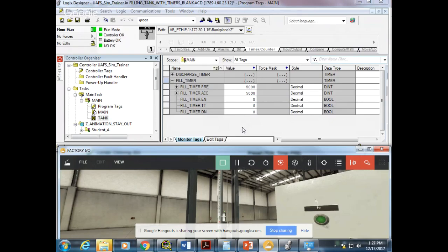So what could I use that for? Let's say I have some kind of mill or machine with a heavy torque load, like a 50 horsepower motor. Okay. And so when I hit the off button, I really don't want to just turn it off. I want to turn it off, but I want to apply the brakes for 20 seconds. And I could use that TT bit to apply the mechanical braking system for 20 seconds after it goes off. You with me? So I could energize a clutch solenoid with that TT bit and apply brakes for a preset time after I turn the machine off.